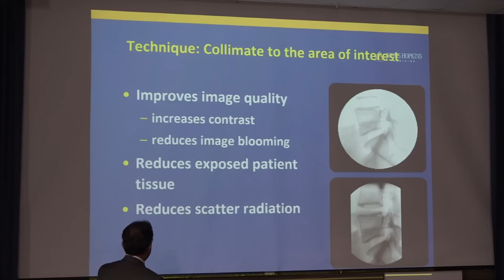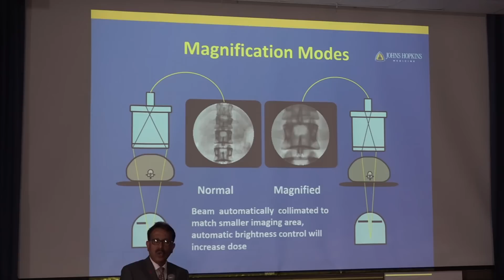Now we also have magnification mode. It means when you're doing a procedure you can magnify anatomy. When you magnify, it will automatically constrict to the area. Because of that, the number of photons reaching the image receptor is less, so it will automatically push the system to generate more radiation. Therefore, if you go into magnification mode, the radiation dose to the patient increases. So another advice we give is to minimize the amount of magnification you use during the procedure, only when it is necessary.